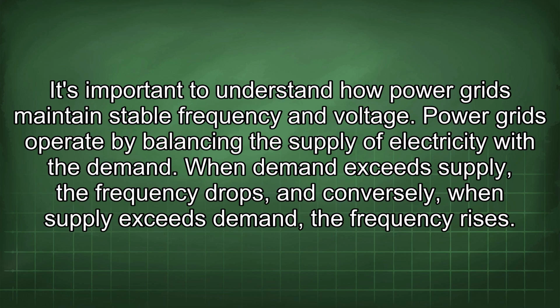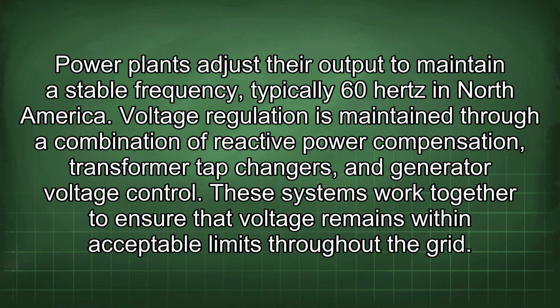It's important to understand how power grids maintain stable frequency and voltage. Power grids operate by balancing the supply of electricity with the demand. When demand exceeds supply, the frequency drops, and conversely, when supply exceeds demand, the frequency rises. Power plants adjust their output to maintain a stable frequency, typically 60 Hz in North America. Voltage regulation is maintained through a combination of reactive power compensation, transformer tap changers, and generator voltage control. These systems work together to ensure that voltage remains within acceptable limits throughout the grid.